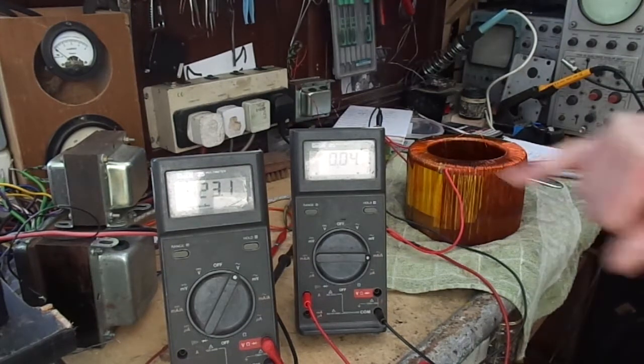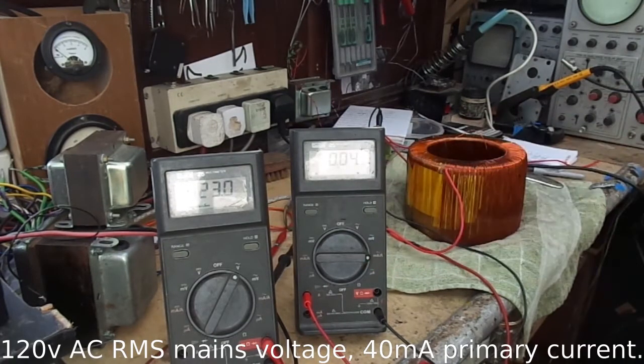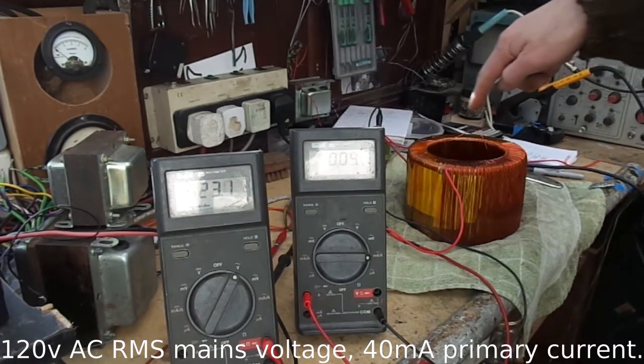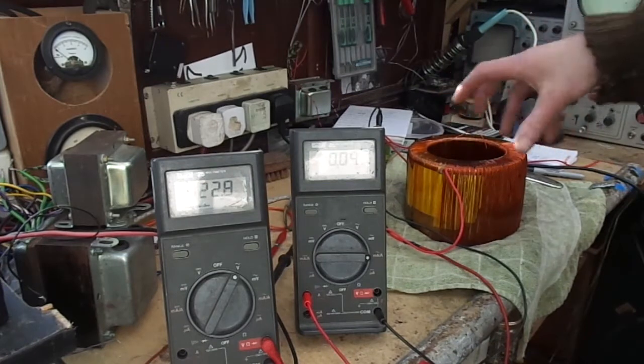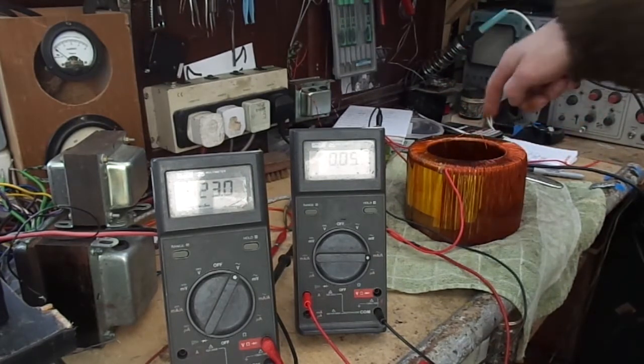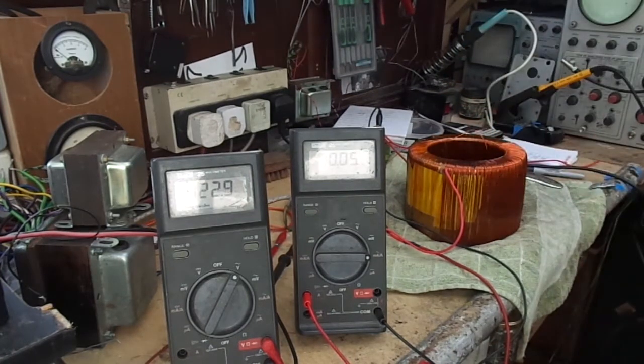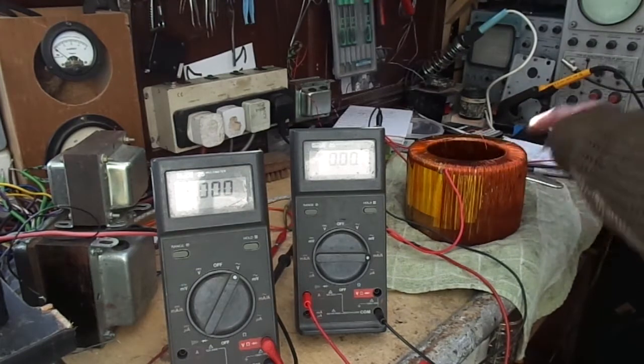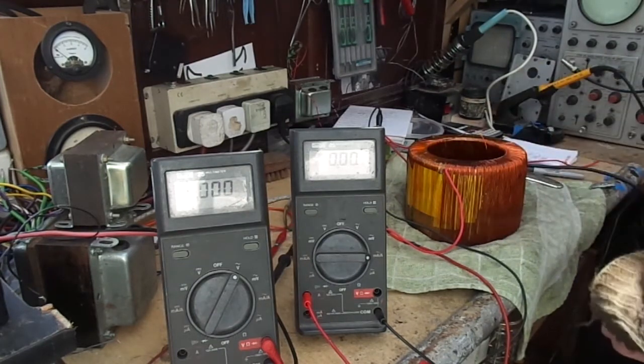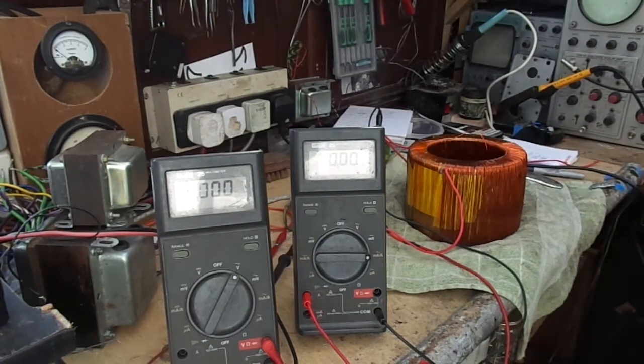As you can see, our current is about twice, so in actual operation we'd have to connect the two halves of the primary in parallel so everything's cushy. Now it's just a matter of insulating this, cutting that off, putting the wire on, insulating it, and then putting on the secondaries.